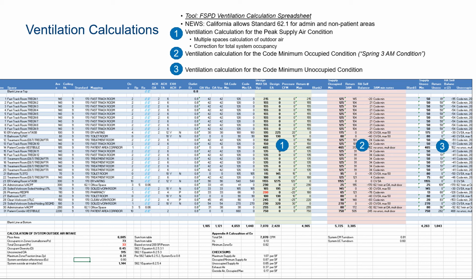Again, if you're doing new controls, it is our standard to interlock lighting occupancy sensors to HVAC so that you can turn down those rooms. OSHPD lets us turn down the rooms to 20%. If you're following standard 170, I guess you can turn them all the way down to 0. But you need to understand what that unoccupied turn down condition is on a room by room basis. And of course, the entire time you're doing this, you need to maintain balance for all the positive pressure rooms in the system and all the negative pressure rooms in the system. So not going to lie, this calculation is an absolute pain in the ass.